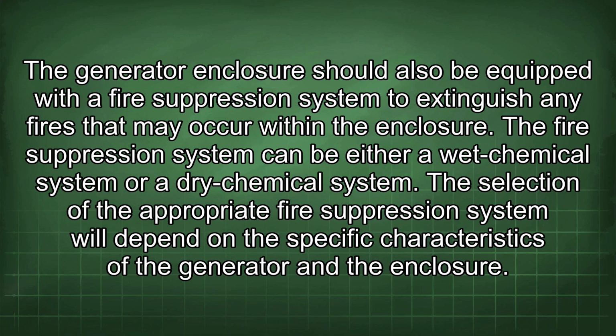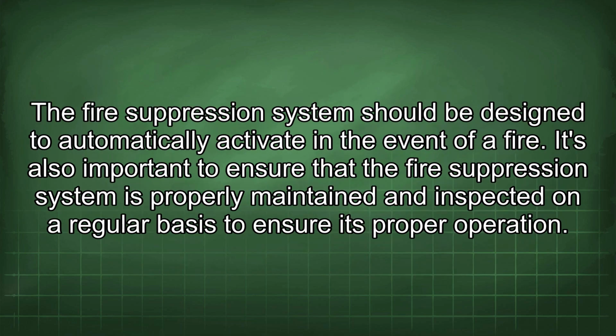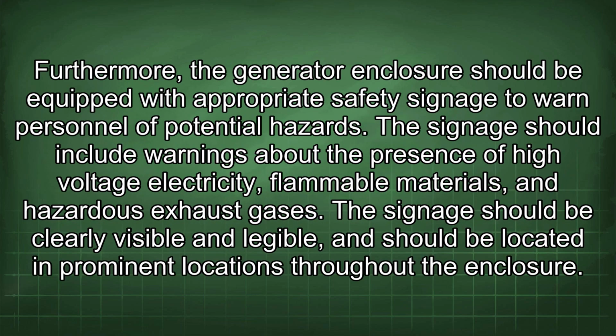The selection of the appropriate fire suppression system will depend on the specific characteristics of the generator and the enclosure. The fire suppression system should be designed to automatically activate in the event of a fire. It's also important to ensure that the fire suppression system is properly maintained and inspected on a regular basis to ensure its proper operation. Furthermore, the generator enclosure should be equipped with appropriate safety signage to warn personnel of potential hazards. The signage should include warnings about the presence of high-voltage electricity, flammable materials, and hazardous exhaust gases. The signage should be clearly visible and legible, and should be located in prominent locations throughout the enclosure.